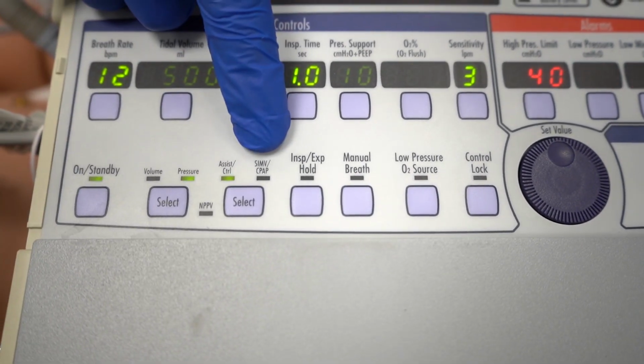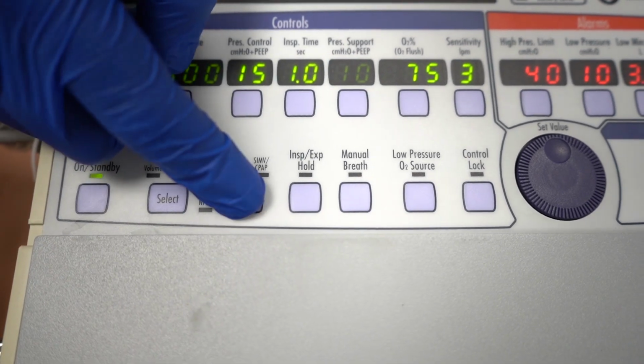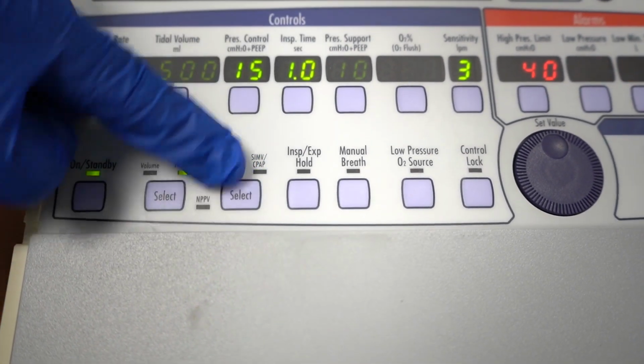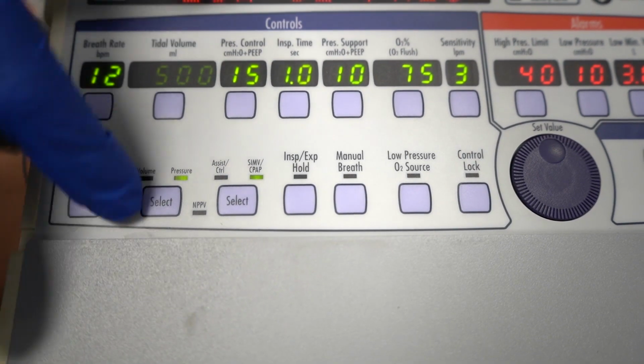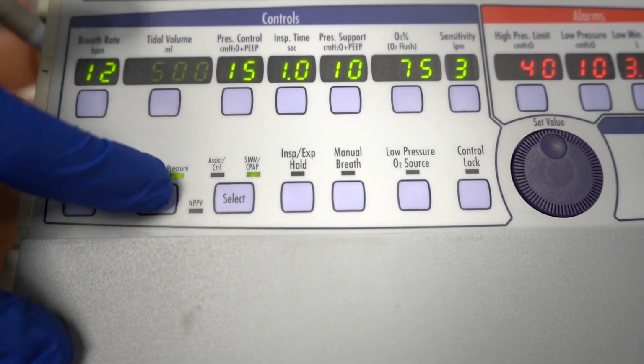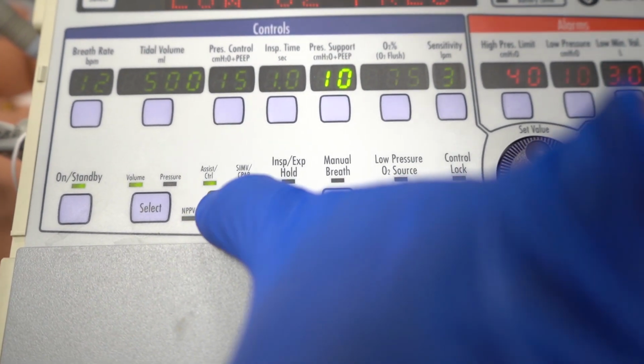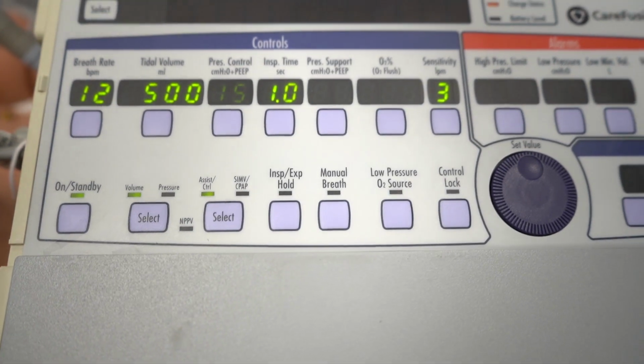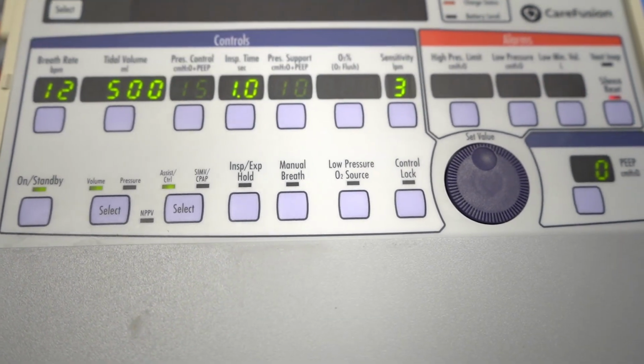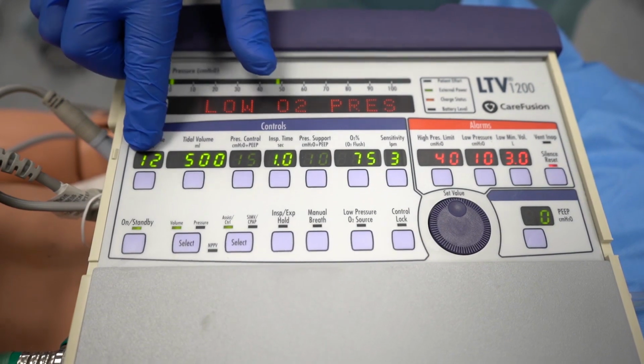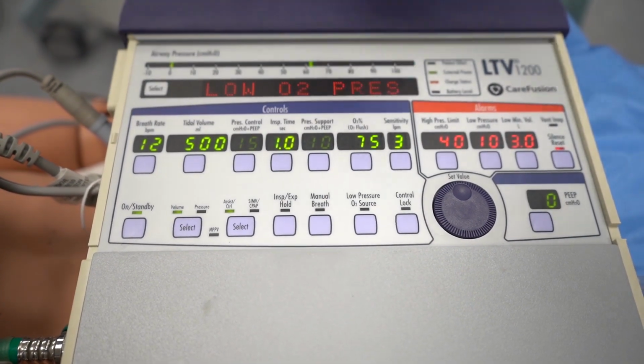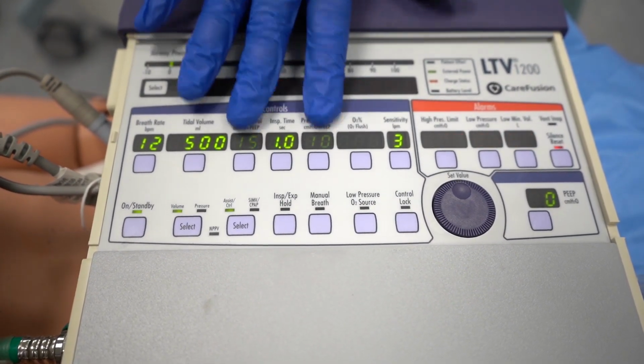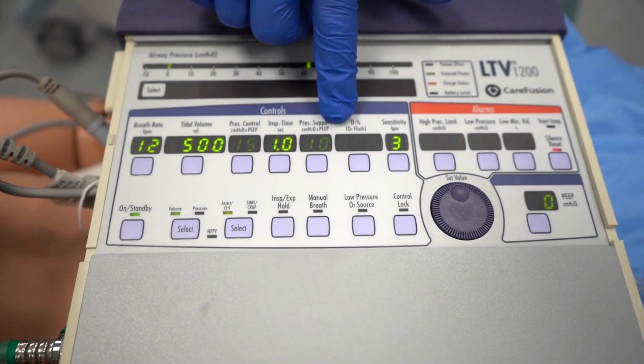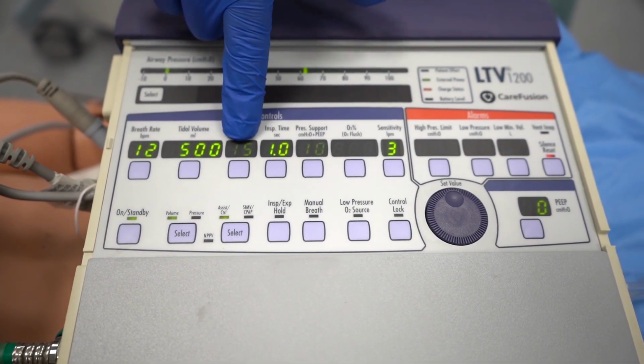Same thing on all these other, so your assist control, SIMV, CPAP are located here. If you want to change that, simply select, wait till it's blinking, and select again. Go back to the volume control, and it's just changing the settings on here. The settings that are lit up are your current settings. The ones that are kind of faded off to the background, those are inactive. So for instance, pressure control is inactive because it's faded to the back.